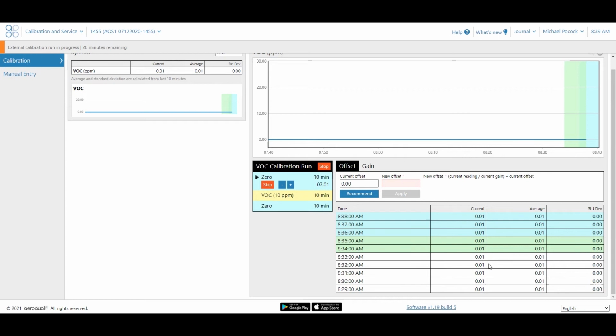Now, if you weren't happy with this number, if this was saying 1 ppm, well, we wouldn't be very happy that our zero air is saying 1 ppm. So in that case, you just simply hit this recommend button, and the software just recommends a new offset for you, and then you just click the apply button. So if you do that, I'll just do it anyway, even though my number's quite fine. It's well within the plus or minus 0.1 that I'd be concerned about. But you just press the apply button.